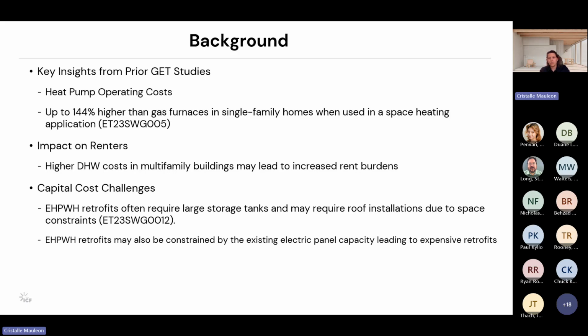And additionally, we anecdotally know that there are multifamily sites which are constrained by the electric panel capacity. And even if they had the space for large tanks, they would require expensive panel upgrades to install the electric heat pump water heater. So these insights from these past studies and anecdotal evidence highlight the need to evaluate alternatives like gas absorption heat pumps for economic feasibility.